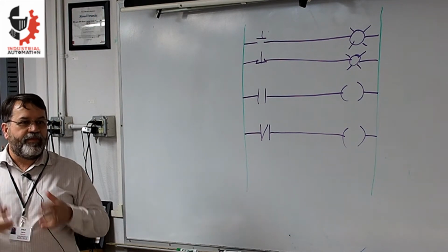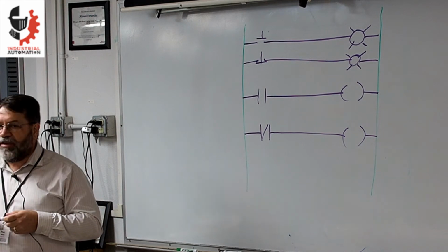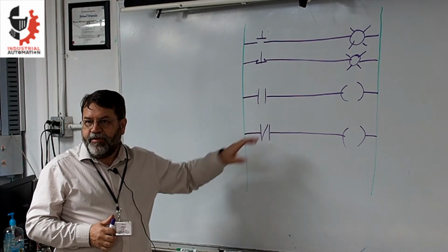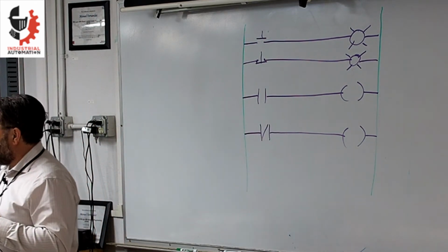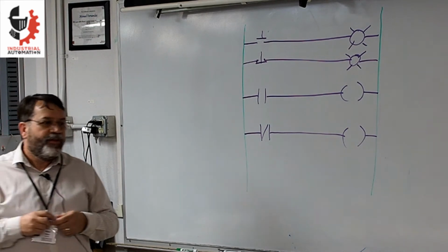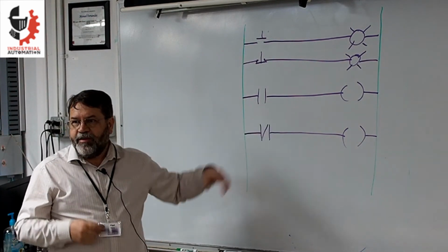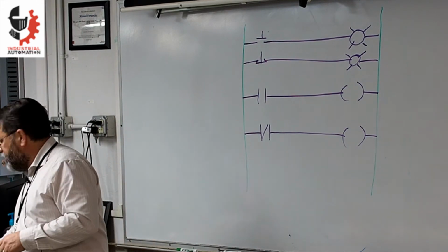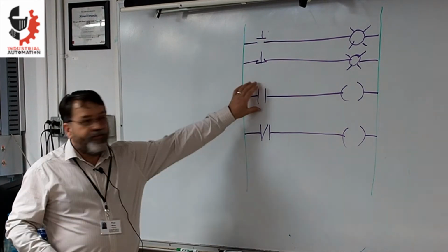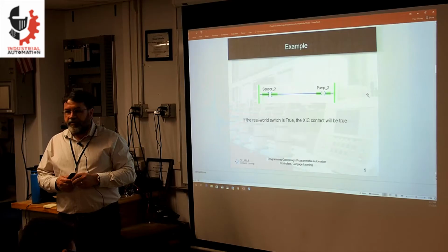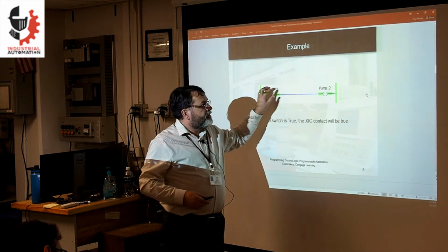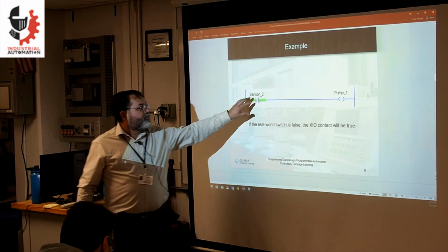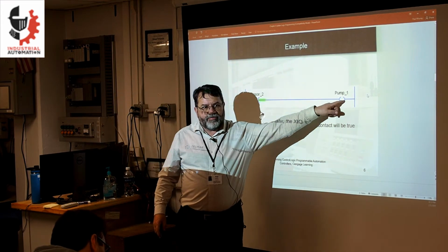So it's kind of like a double negative, and when you get into actually using normally closed inputs, a lot of times it just works backwards the way you think you have it. So a lot of times you have to try it one way and see what's happening and then go back and switch it, because it's kind of a double negative. I always try to use normally open because this is a normally open input. If it goes hot, then your output to that pump goes hot. Normally closed, if it goes hot, that pump goes off.